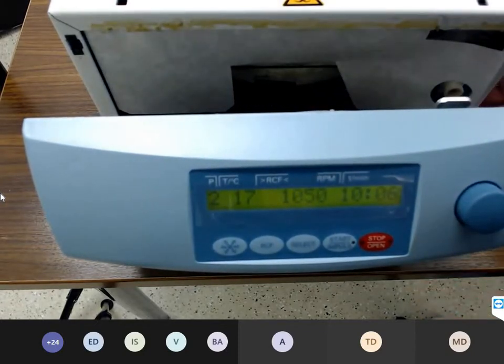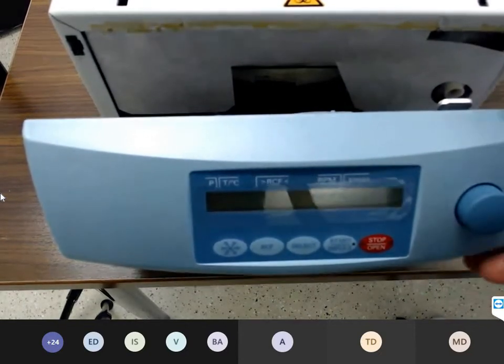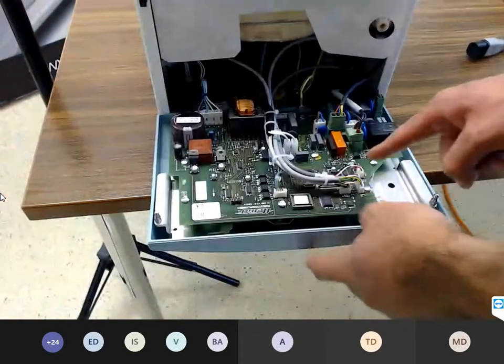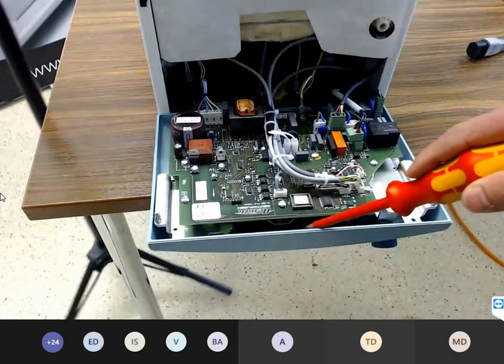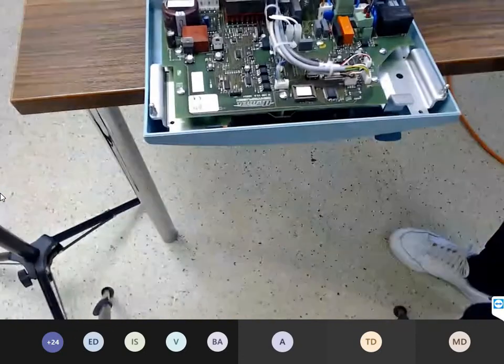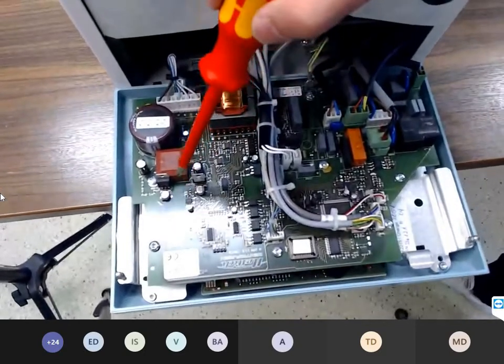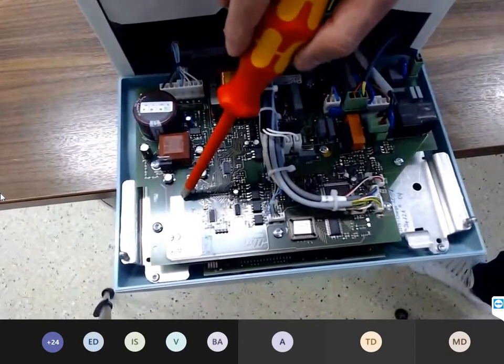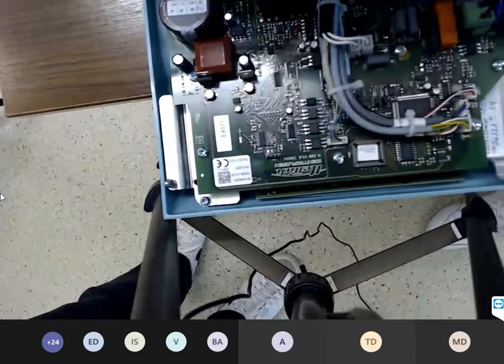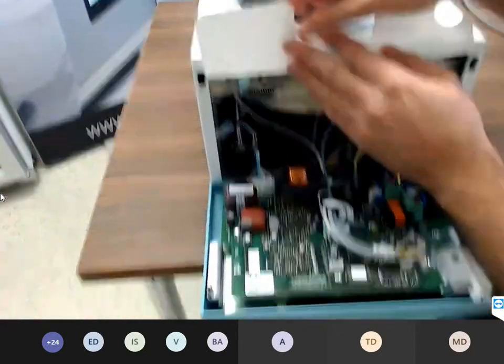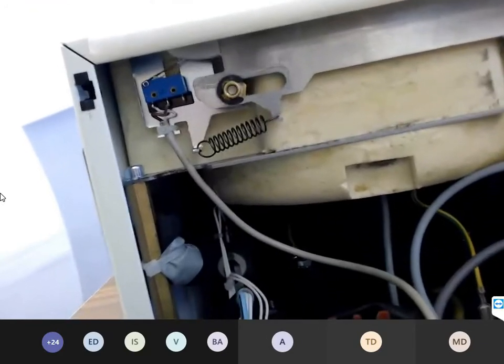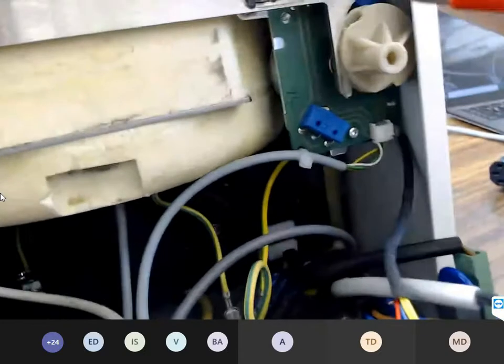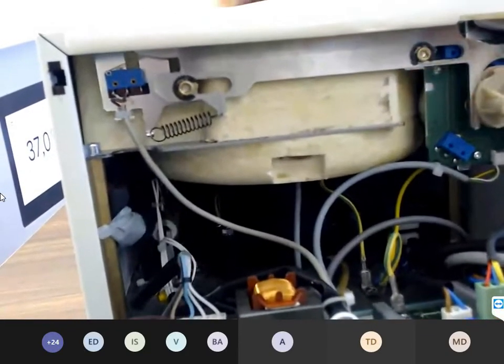Now we go into the centrifuge, switch off. We have here the front panel with the electronic board. Behind the electronic board is the control board. We can see here the spare part number. Behind this foil is the lid lock complete. On the right side, the motor, and on the left side only a micro switch. If you have an issue with the lid, please change it completely. It's easier for you.